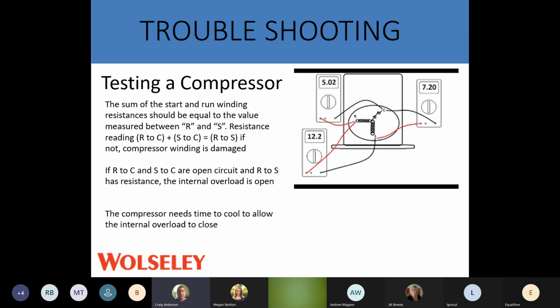Compressor, everything's running, contactor is pulled in, fan is running. I have 220 going to my compressor, but nothing is operating. So first thing we're going to check for burnt wires on either end. Wires look good. Now we're going to check the resistance in our compressor. So when we're checking our resistance, we can check them on the wires going to the compressor, or we can check them right on the compressor. Proper reading is right on the compressor. That way we're eliminating a wiring harness or anything like that.